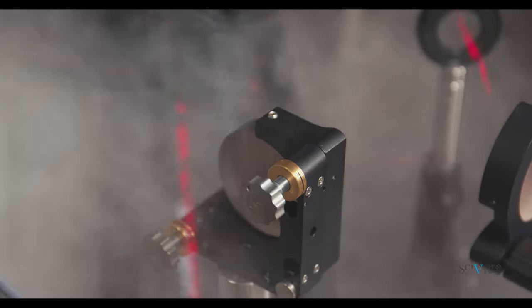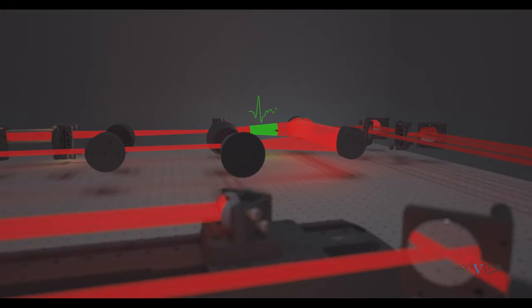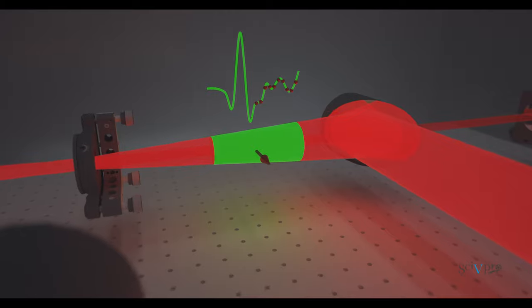The pump beam travels towards a delay line, which is used to introduce a relative time delay between the pump and the probe pulses. Different delays allow sampling different data points from the terahertz signal exiting the sample, meaning that the terahertz output signal can be reconstructed by sweeping the delay line.